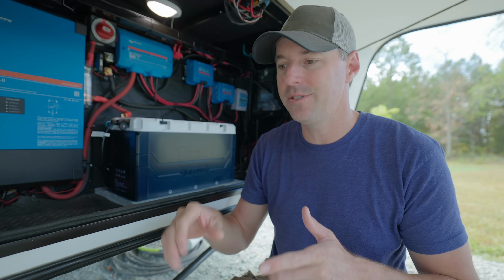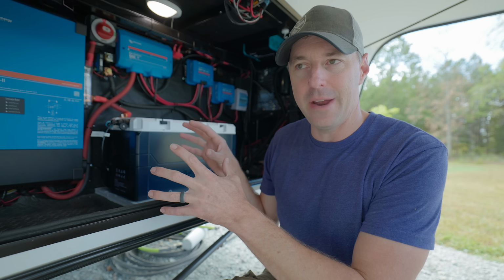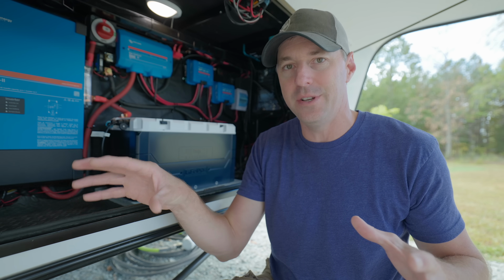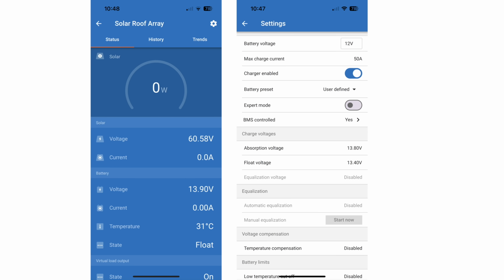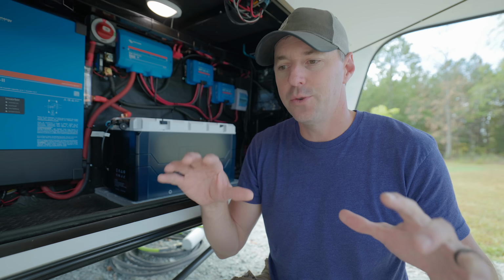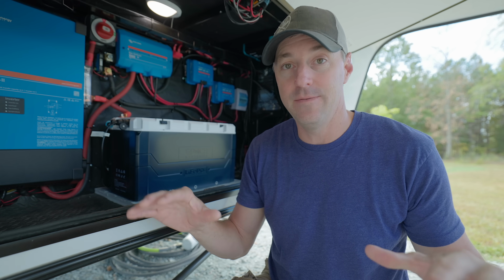The second thing is that the voltage settings for this battery are lower than other lithium batteries I've used. They recommend running it at 13.8 for the absorption voltage and 13.4 for the float voltage, which was lower than the previous batteries I had in here before, and I hadn't changed any of those settings. Once I changed the settings, I didn't get that high voltage anymore.